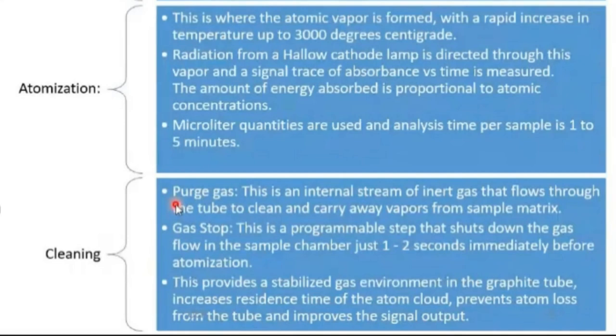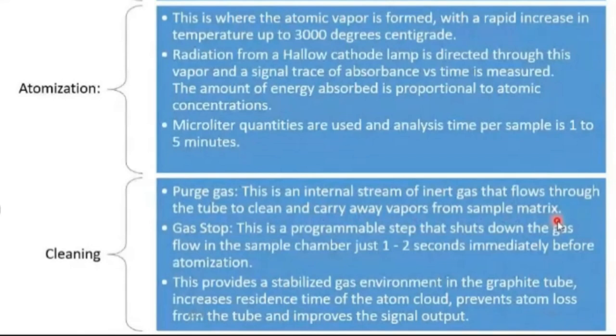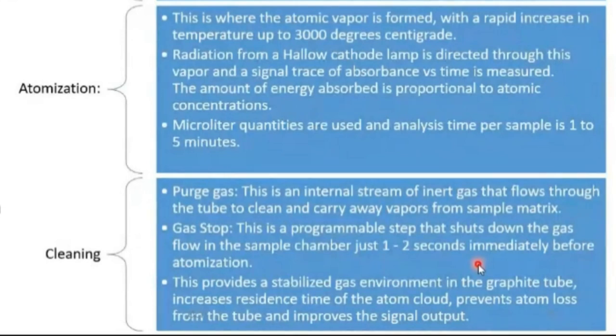For cleaning, a purge gas is used — an internal stream of inert gas (such as nitrogen) that flows through the tube to clean and carry away vapors from the sample matrix. Then there is a gas stop: a programmable step that shuts down the gas flow in the sample chamber just one to two seconds immediately before atomization.